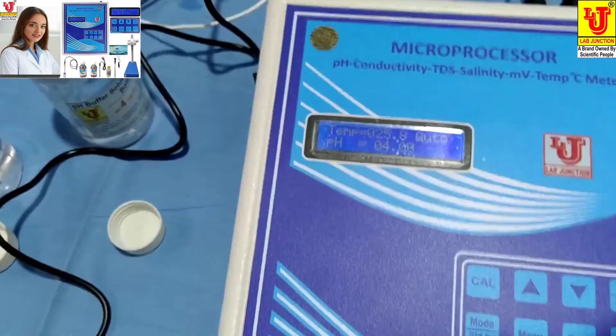Suppose it is 3.83. Again press enter. Again press enter. 4 is calibrated. If you go up, then buffer 3, 9.2, is required if you want to do 3-point calibration. In this meter, 2-point calibration and 3-point calibration facilities are available. Now pH is calibrated. Quit from the back key. This is your pH result. Now this is in 4 pH.